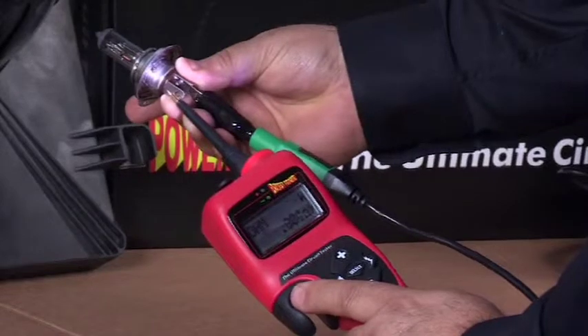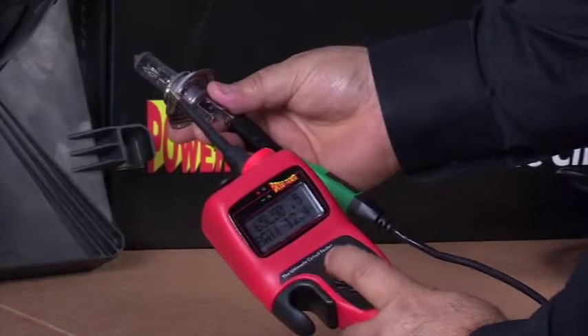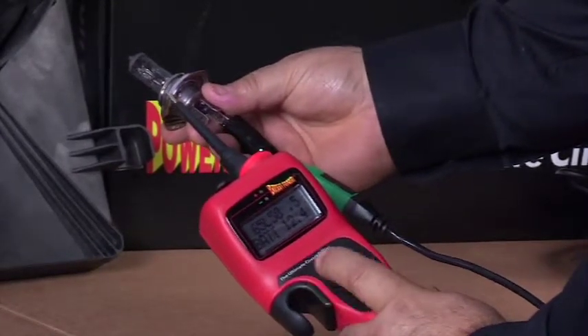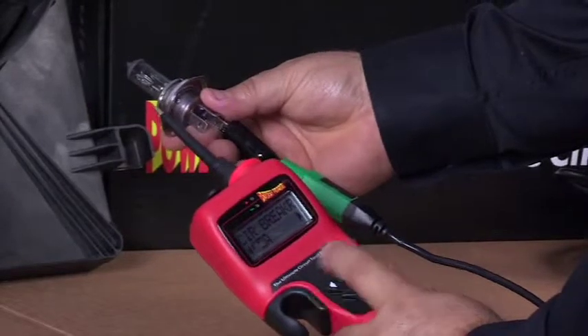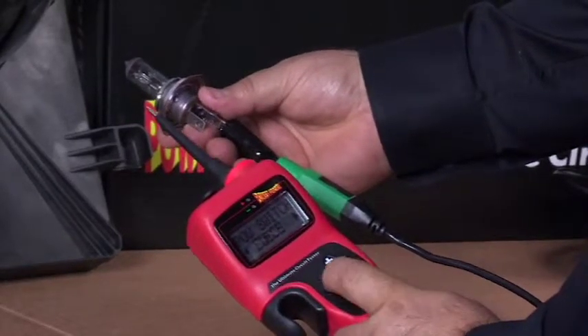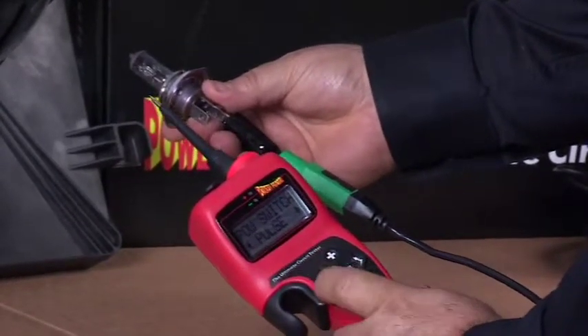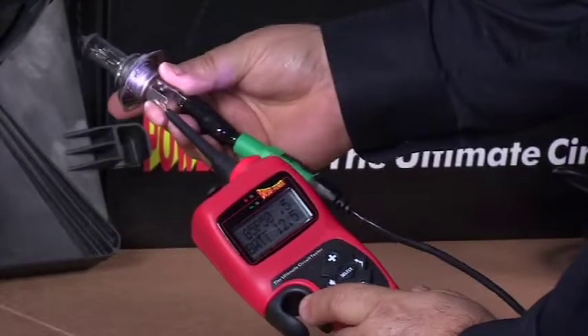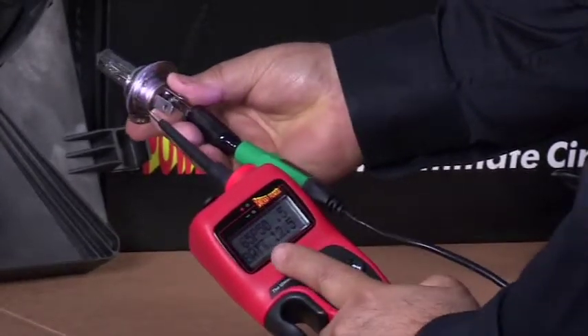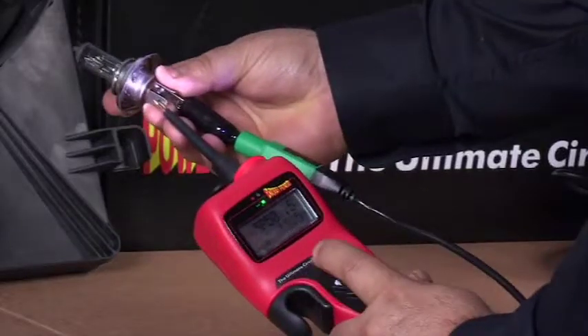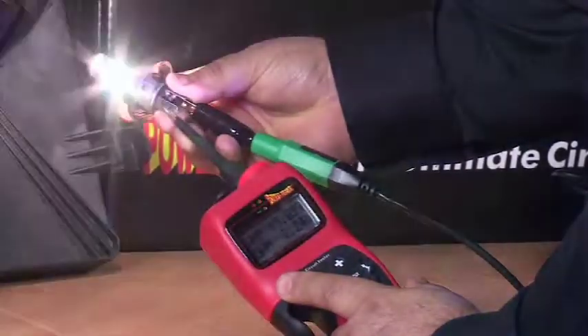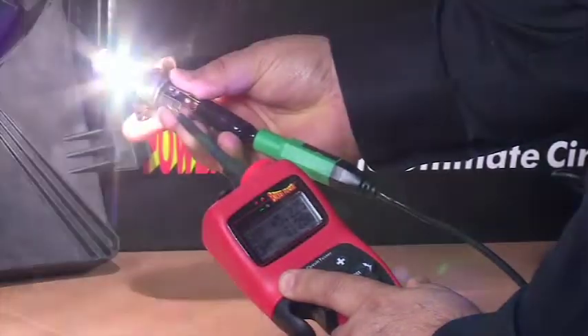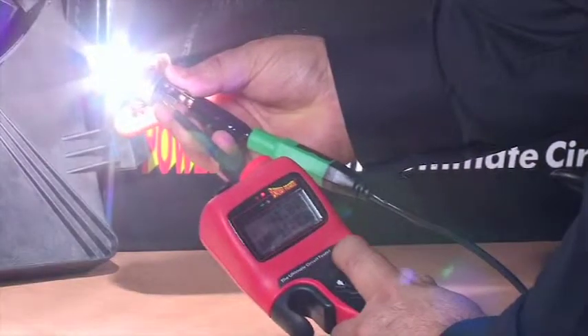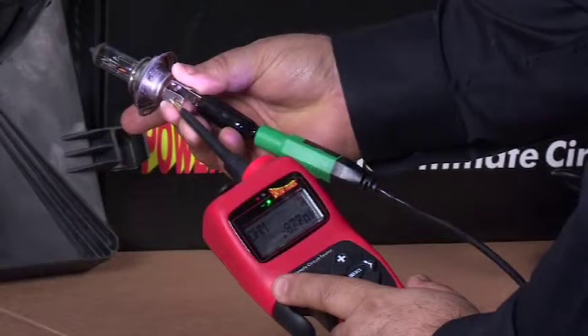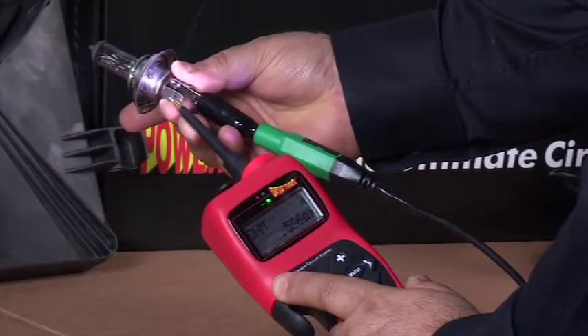To pulse a circuit with power, set the power switch preference to pulse like this. Press select, down, right, until the screen shows pulse. Press select. Notice the P in the preference line. Press the power switch and the power is pulsed in half-second increments to the probe tip. Turn it off by pressing the power switch again. It also works the same when applying ground to the probe tip.